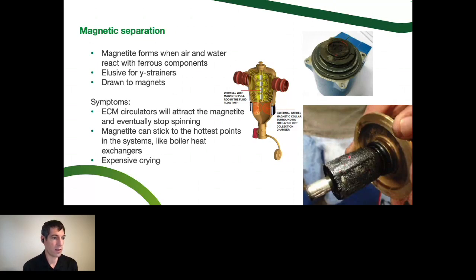And what happened is it created some magnetite from the continued rust from the inside out of the system that all accumulated right on our ECM pump and caused it to fail. So we definitely don't want to be replacing commercial ECM pumps in the buildings that we design and install and service. So just having a bigger magnet upstream of that is what we're going to do to prevent the magnetite from getting stuck in the really expensive stuff like the commercial ECM circulators or caking to the inside of a boiler heat exchanger, as an example.